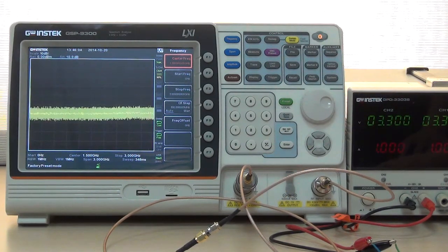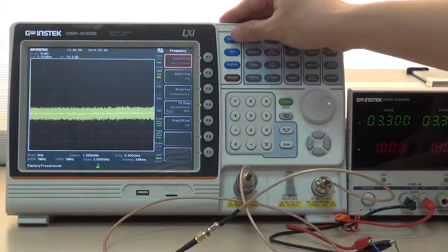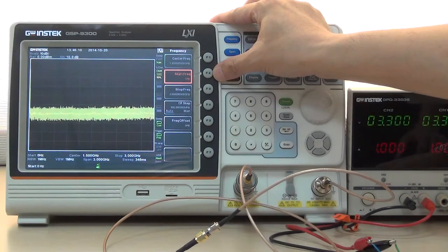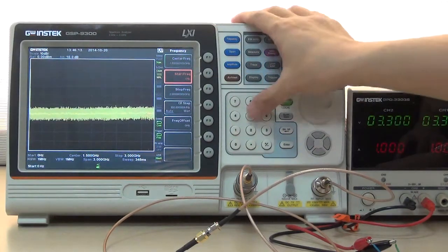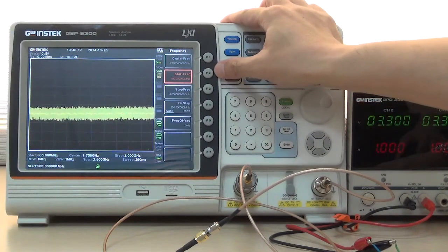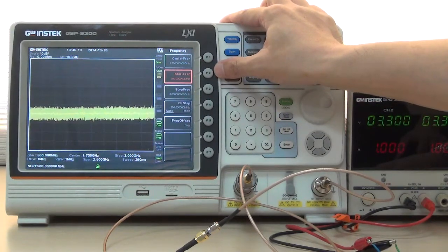To begin the operation, press Frequency and select F2 Start Frequency and input 500 MHz to set Start Frequency as 500 MHz.